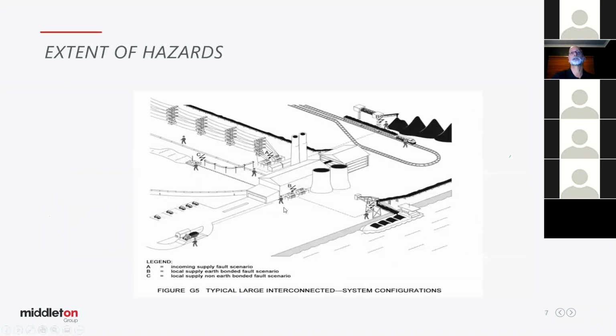This slide's just to show you the extent of, let's say we have a fault in the switch yard in the centre of this industrial area. We'll have cables that are connecting out to train loaders or out to ship loaders, out to other areas. All of these could potentially be bonding all of the earthing systems together. And if we have a voltage created at fault A here, that voltage can be transferred through all of these earthing elements out to other areas that are quite far away from the actual fault. As we've seen on the last slide, essentially the further you are away from the fault, the higher that voltage may be.